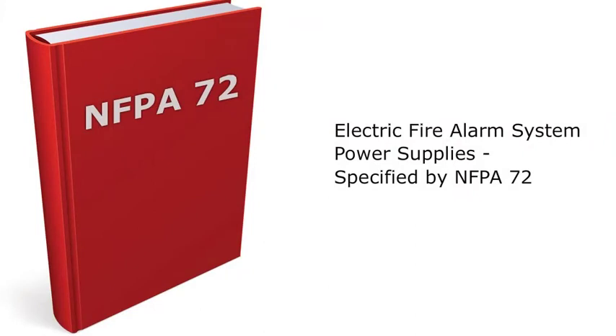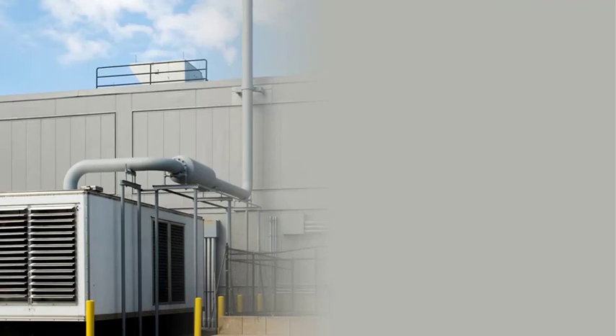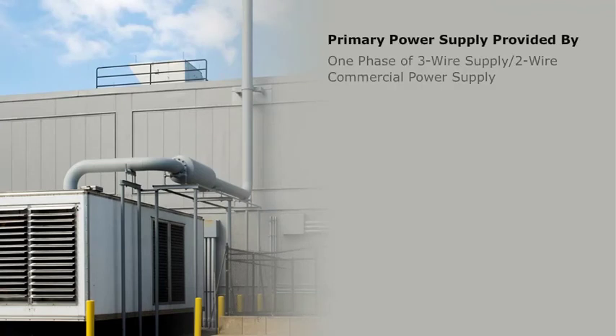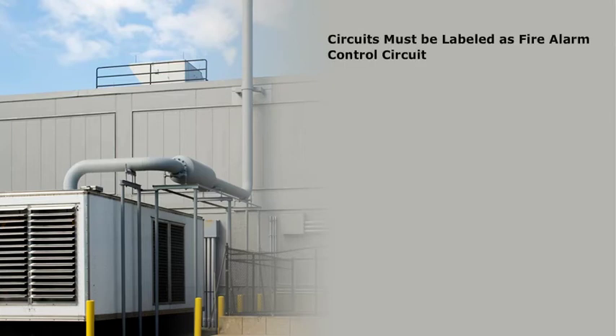The primary power supply can be provided by either one phase of a three-wire supply, or a two-wire commercial power supply, and must be on a dedicated branch circuit. The power supply can also be through a generator. Circuits must be labeled as fire alarm control circuit, and available only to authorized personnel.